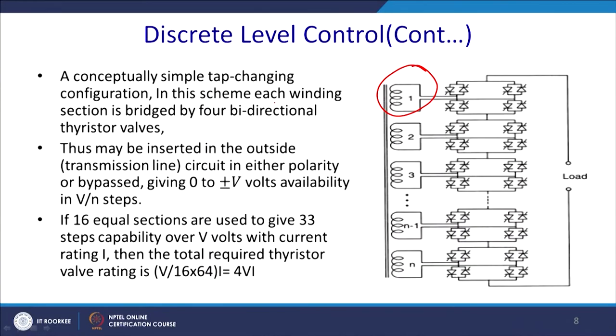Conceptually, in the simple tap-changing configuration in this scheme, each winding section is bridged with 4 bidirectional thyristor valves. So, these are the 4 bidirectional thyristor valves. You can allow current to pass through these switches, through this magnetics, or you can simply bypass this magnetics. You have a choice. Thus, it may be inserted in the transmission line with either polarity or bypassed, giving 0 or plus minus V volts, in n number of steps.